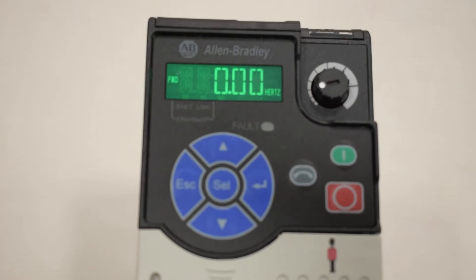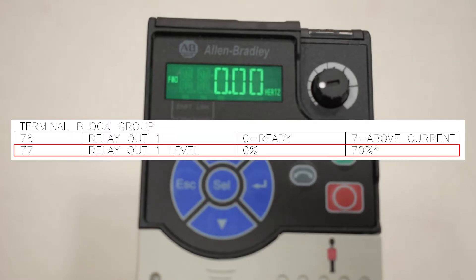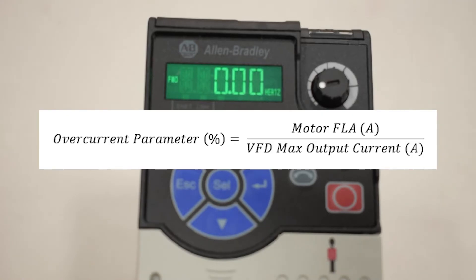Navigate to the VFD parameters table on the LMEC control drawings. The motor overcurrent parameter is located at T077. This parameter value is calculated by dividing the motor FLA by the VFD's maximum output current.